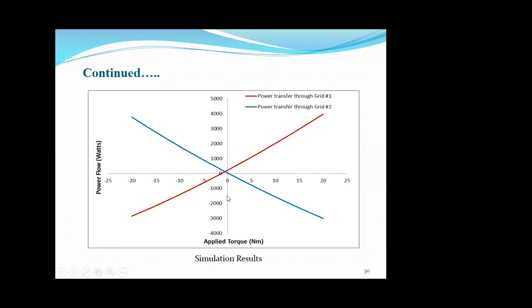This graph clearly shows that the power flow through the VFT is controllable and bidirectional, and directly proportional to the torque applied by the DC drive motor. If you also plot the power supplied by the DC drive motor, in both cases you will get a linear graph, showing it is linear and directly proportional, as we derived in our modeling part.